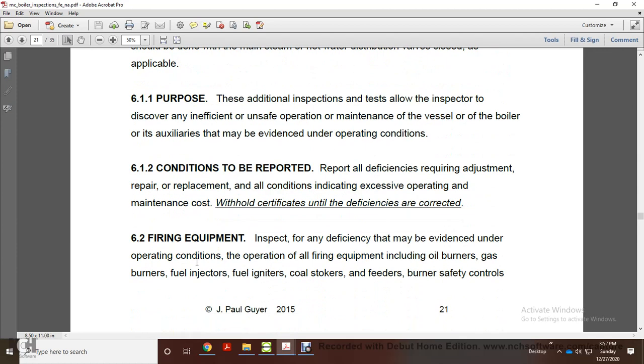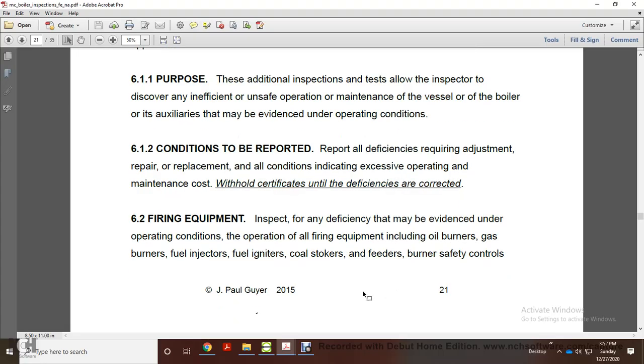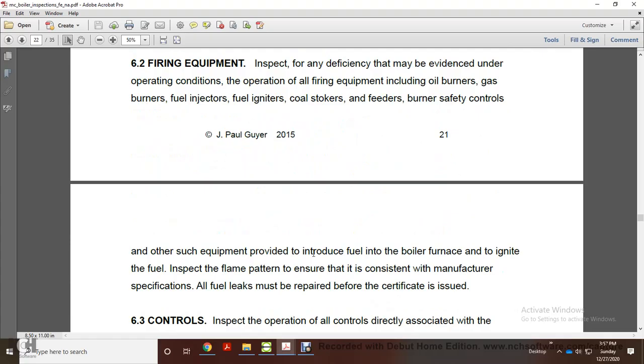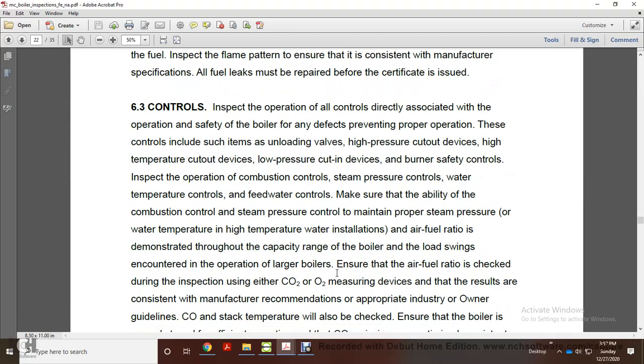Alright, 6.2 Fire equipment. Inspect any other deficiency that is evident under the operating condition. Fire equipment includes oil burners, gas burners, fuel injectors, igniters, coal stokers, feeders, burners, safety controls, and other equipment. Introduce fuel at the burner face to ignite the fuel and inspect the flame pattern to ensure it is consistent with manufacturer specification. All fuel leaks must be repaired before a certificate is issued.